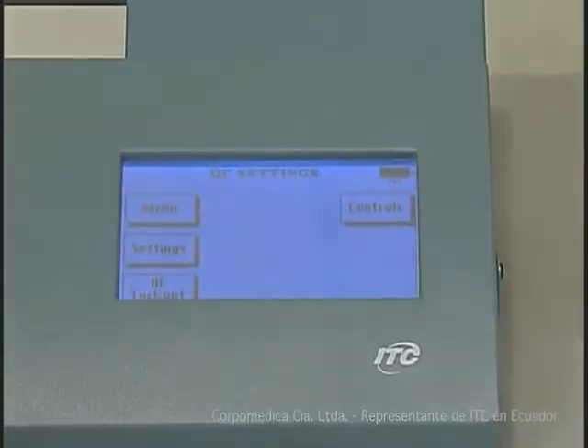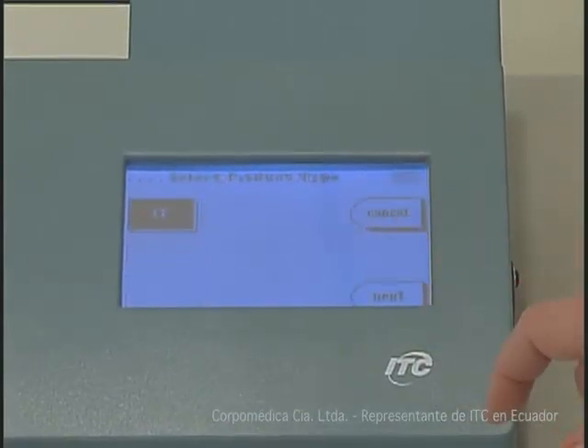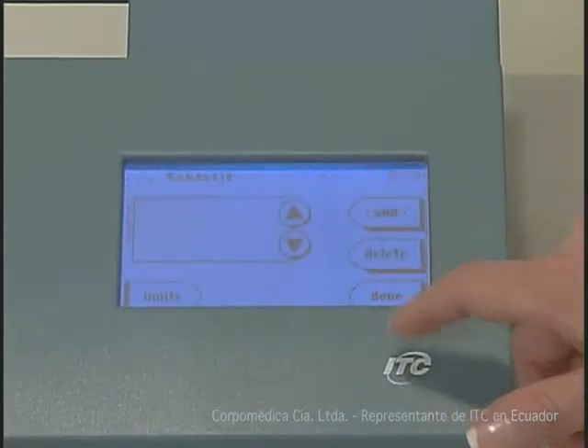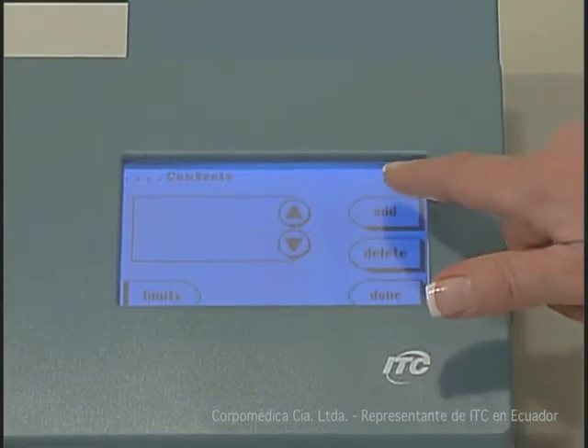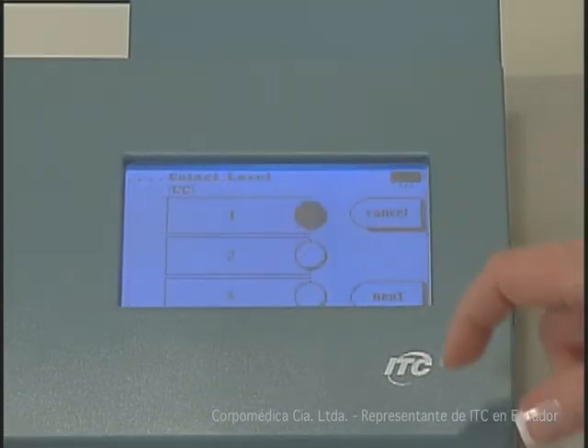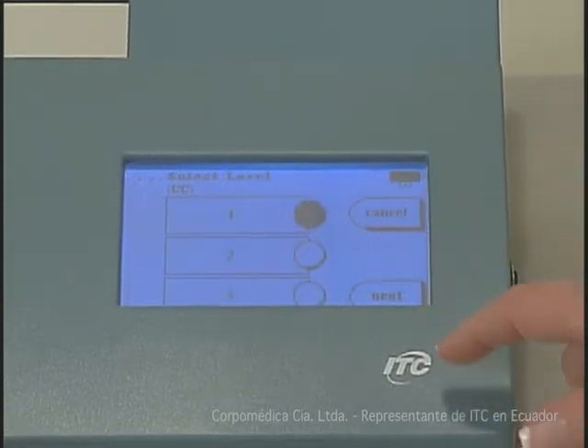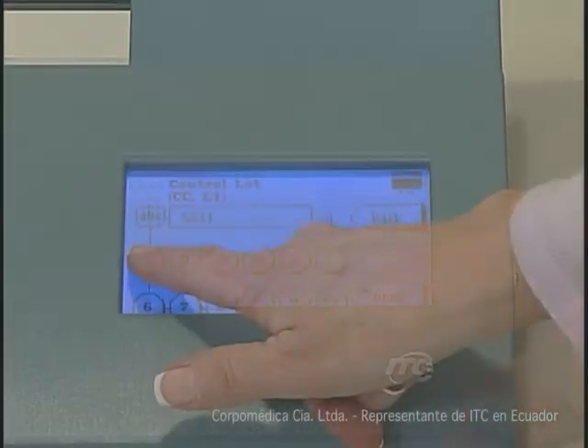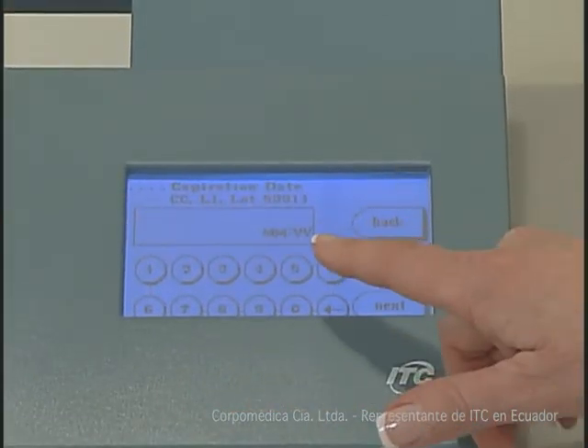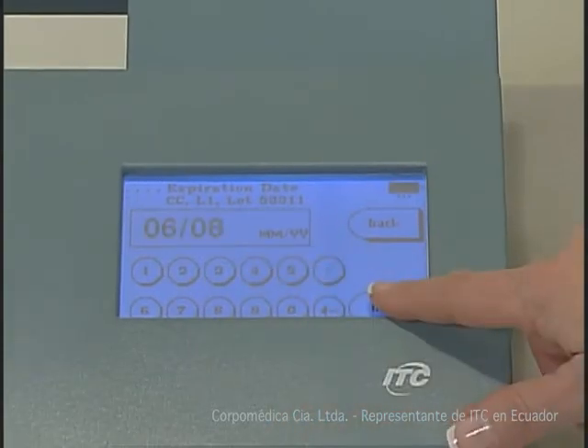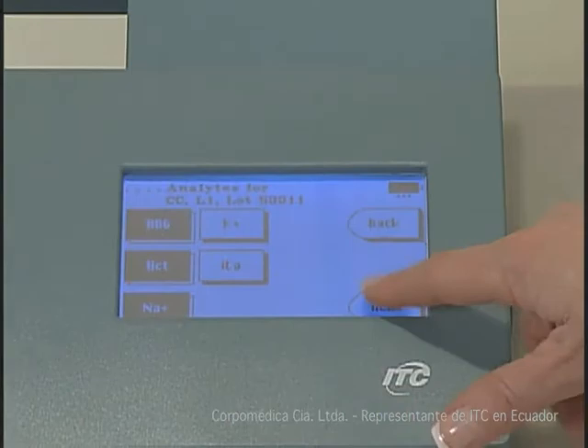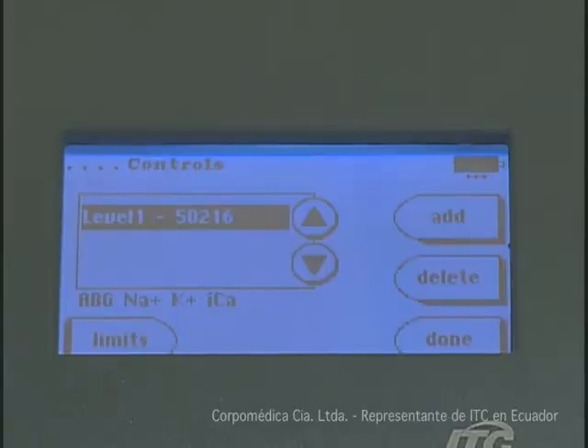Press QC. Press Controls. Select the product type and press Next. To set up a new control, press Add. Select the control level and press Next. Enter the control lot number and press Next. Enter the control expiration date and press Next. Select the analytes to be measured and press Next. Enter or barcode scan in the control limits and press Done.